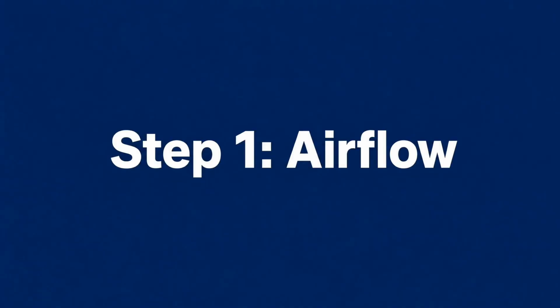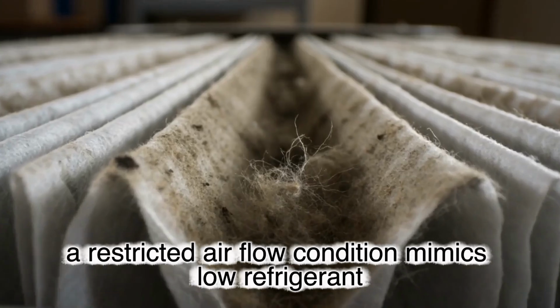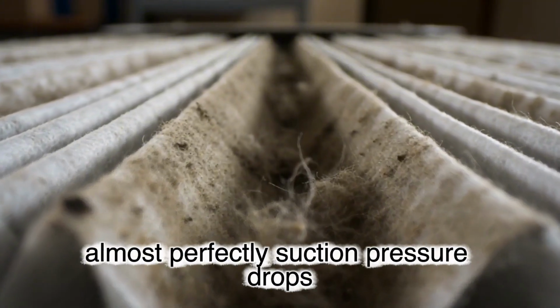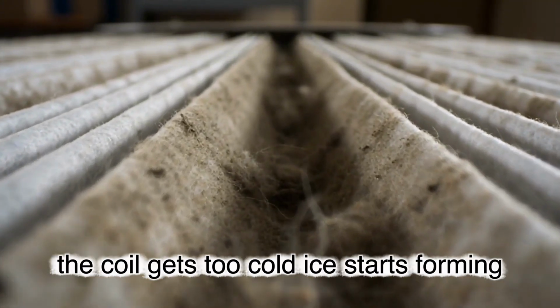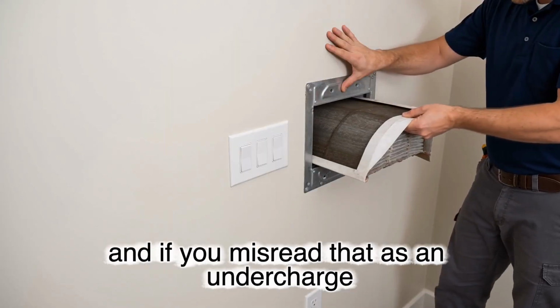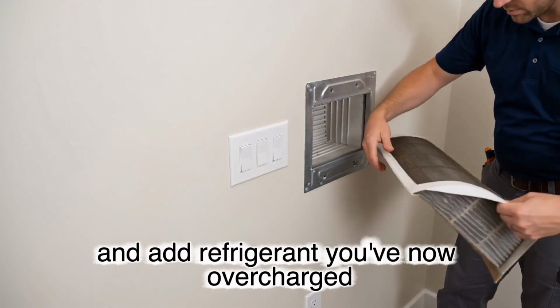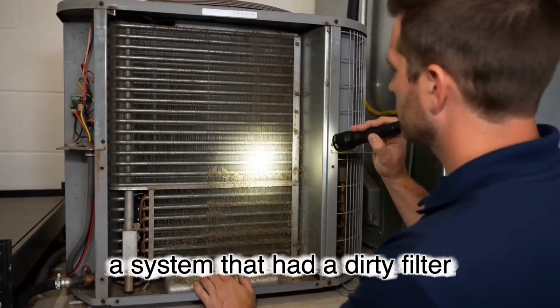Step 1. Airflow first. Here's why. A restricted airflow condition mimics low refrigerant almost perfectly. Suction pressure drops, the coil gets too cold, ice starts forming, and if you misread that as an undercharge and add refrigerant, you've now overcharged a system that had a dirty filter.